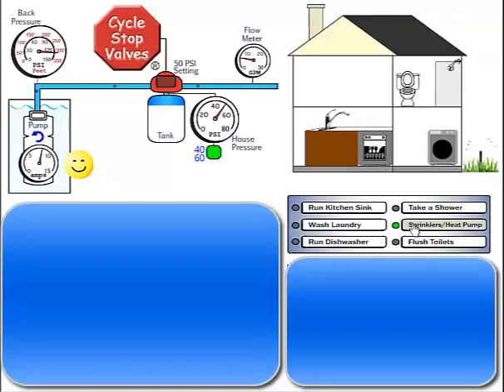Many people do not understand how a tank with only 1 gallon of water can safely supply things like 50 to 60 intermittent toilet flushes a day. And while it is true that with the small tank, the pump will cycle for each intermittent flush, toilet flushes are rarely intermittent. If you stand there and flush a toilet 100 times in a row, the CSV will only let the pump cycle once, keeping it running continuously until after the last flush.